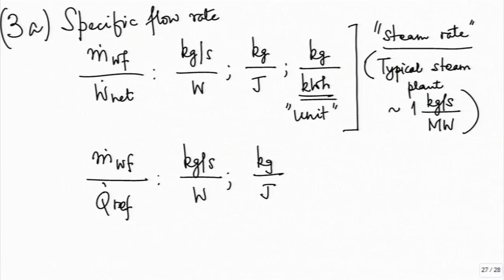If you suddenly get a value of 10 kg per second per megawatt or 0.1 kg per second per megawatt, do check your calculations again because you are likely to have made a mistake. This is for steam power plants with the typical parameter range used today. If you use low-temperature waste heat — say boiling temperature 120–130°C — that is an atypical set of parameters and the steam rate may be much higher. If you are far from this ballpark value, verify that you have some reason to be so off.